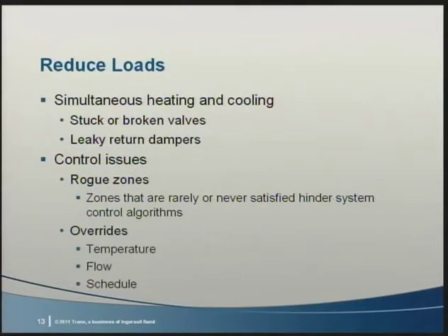Did someone forget to adjust the schedule and forget to put it back? We've all been in meetings where it was too hot or too cold. Maybe it was a sluggish control or a system that couldn't compensate for the load fast enough. So someone went over to the controller on the wall and made a massive change, or the building operator might have overridden a schedule or a set point in the system. The event's now over. Did the room settings get restored? Overrides create rogue zones. Is there an office with its set point a lot lower than the others? You might not ever get to use your reset strategies if the president's office is always set to 60 degrees. Remove these overrides whenever it's possible and prudent.